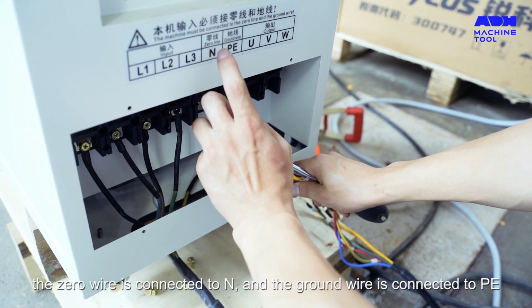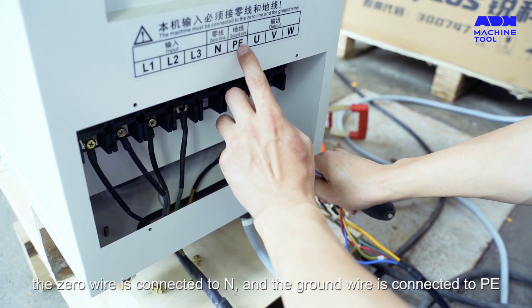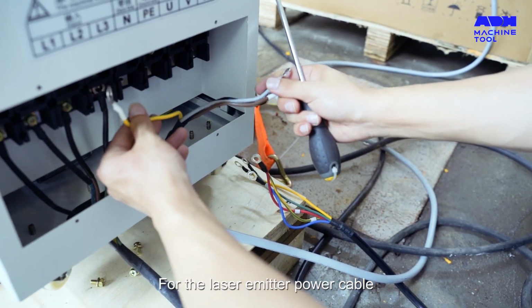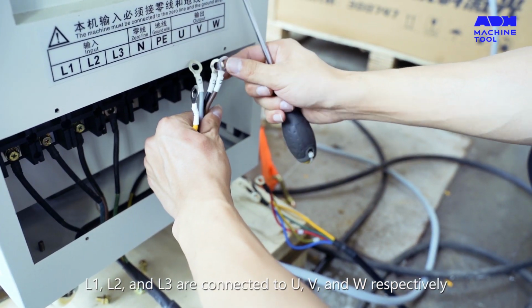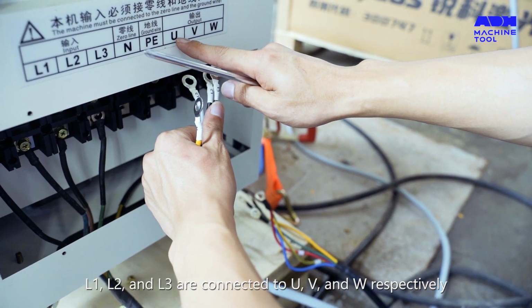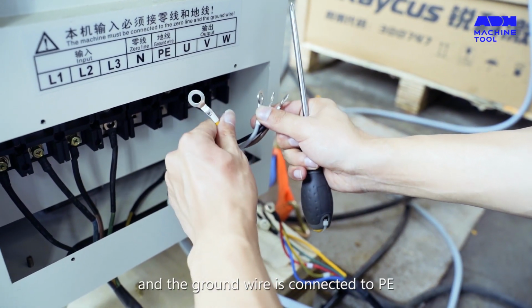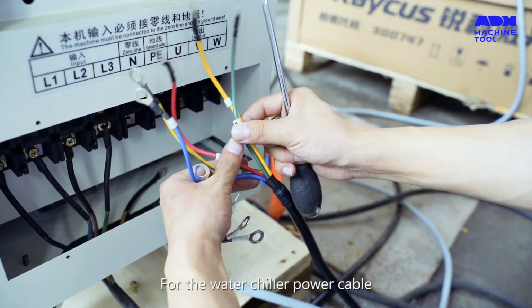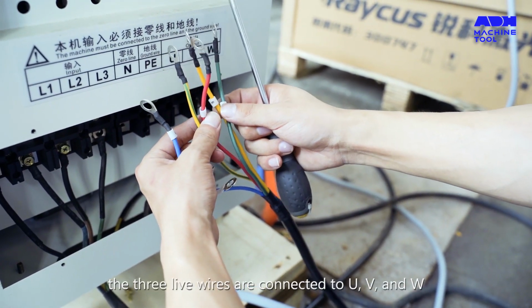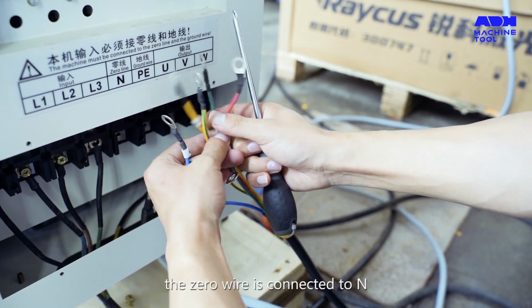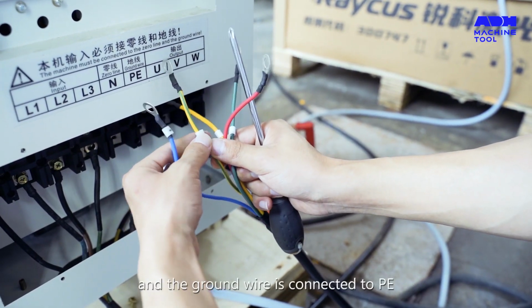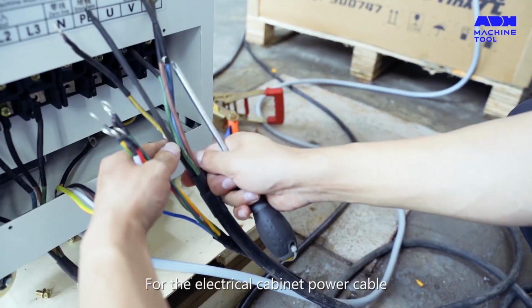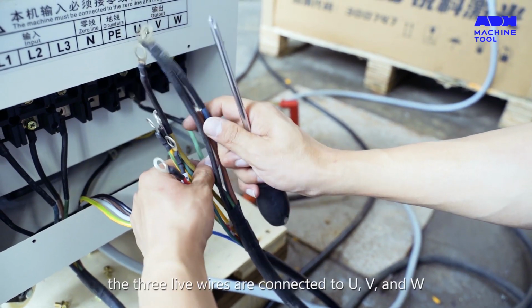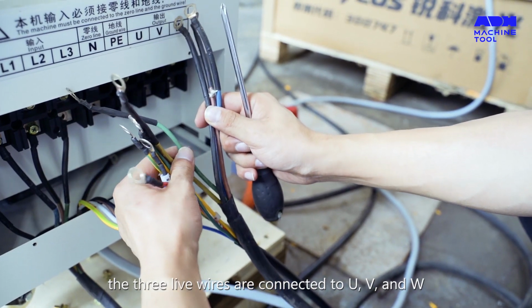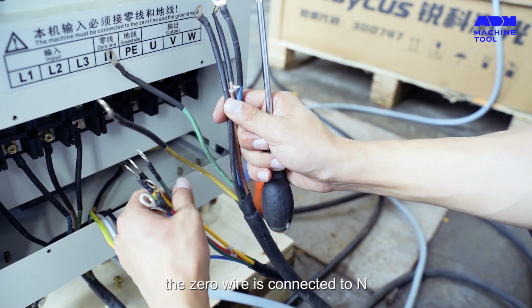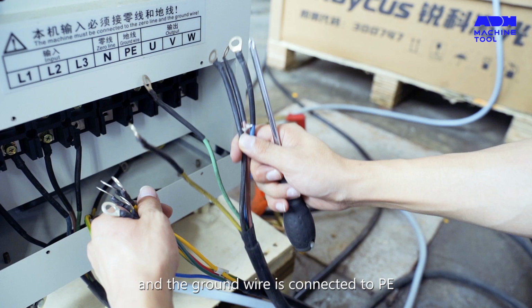The zero wire is connected to N, and the ground wire is connected to PE. For the laser emitter power cable, L1, L2, and L3 are connected to U, V, and W respectively, and the ground wire is connected to PE. For the water chiller power cable, the three live wires are connected to U, V, and W. The zero wire is connected to N, and the ground wire is connected to PE. For the electrical cabinet power cable, the three live wires are connected to U, V, and W, the zero wire is connected to N, and the ground wire is connected to PE.